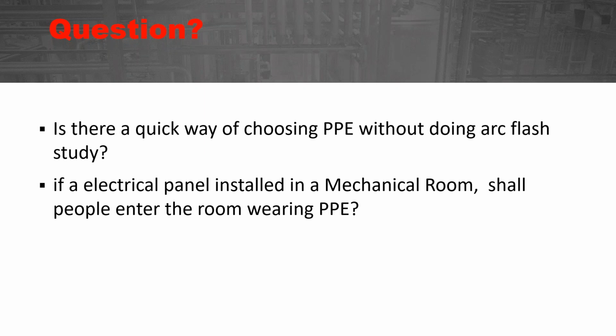One of the things I would do real quickly is look at the PPE category method. You could look at the upstream transformer or estimate the short circuit current going into that panel, and since you know the voltage, you would know if it's been maintained properly or not, especially if you own it. So I would see if I could get a guesstimate of the appropriate PPE. The other thing you could do is not open the door and not work on anything in that panel live until you get an arc flash study done. You could put a policy in that says anytime you're going to work on this panel, you have to put it in an electrically safe work condition and work on it de-energized. So there's a couple of options for you.